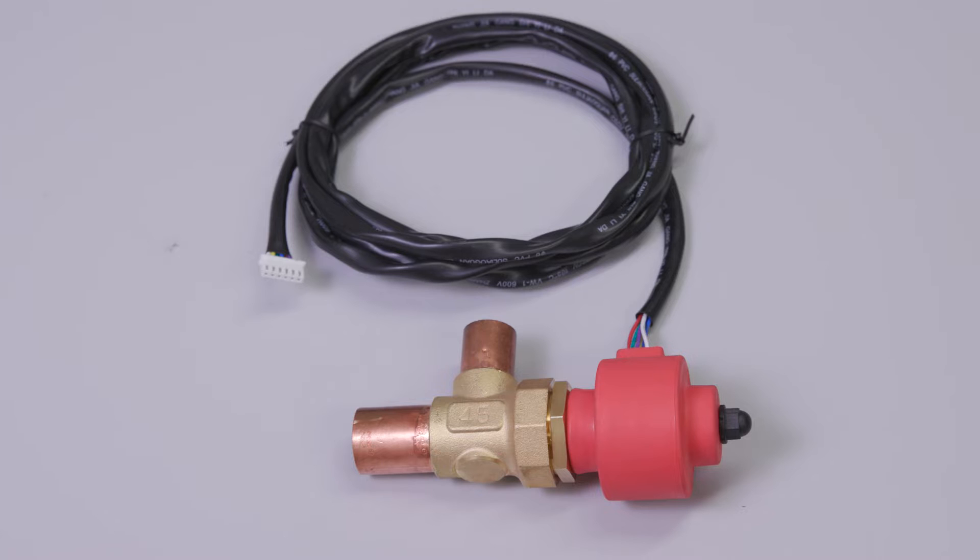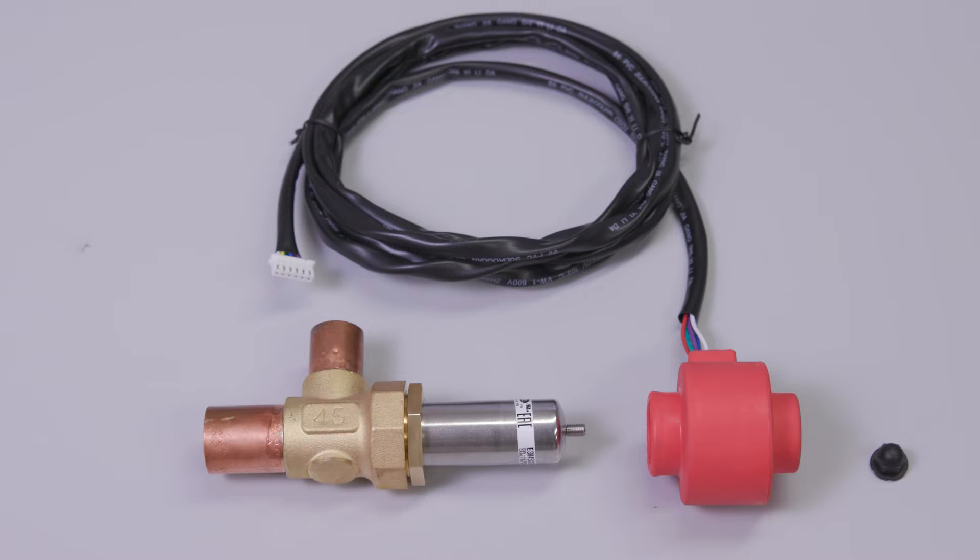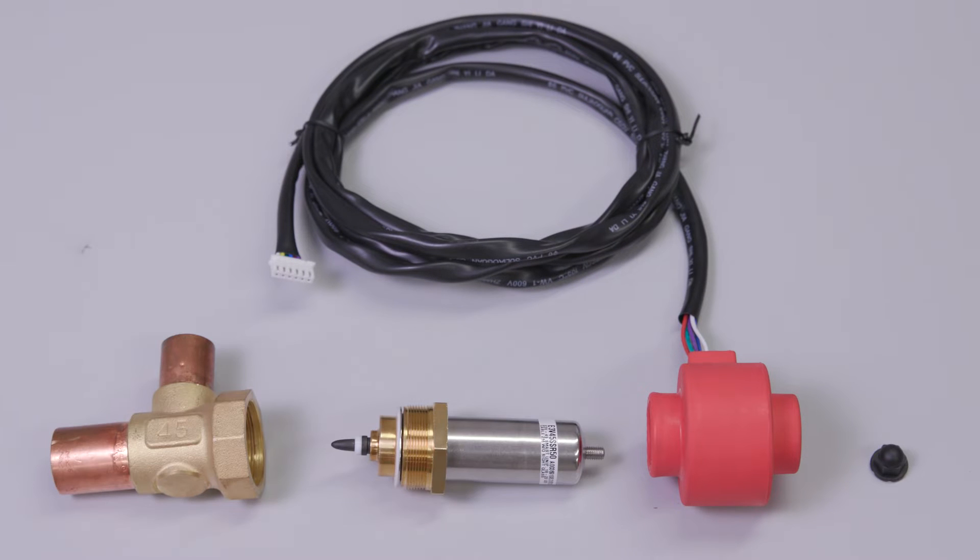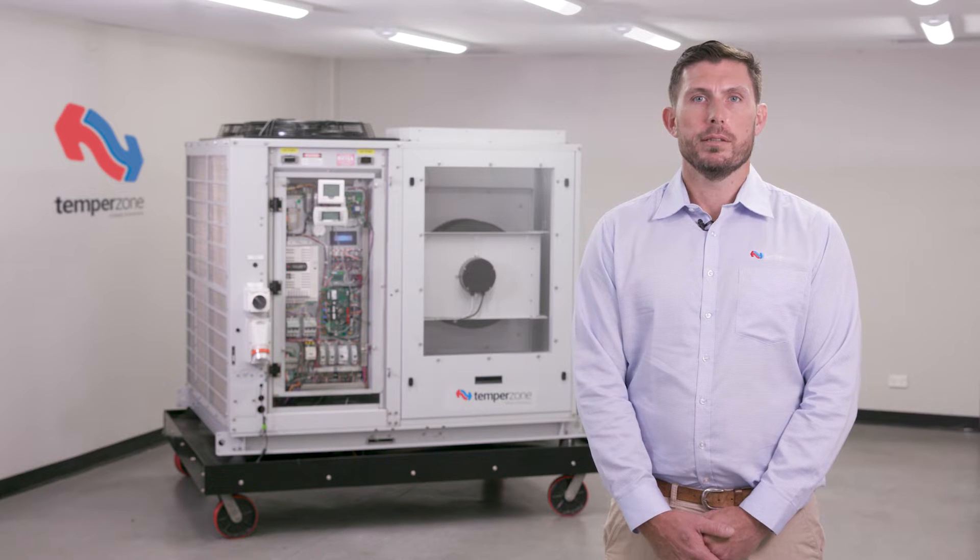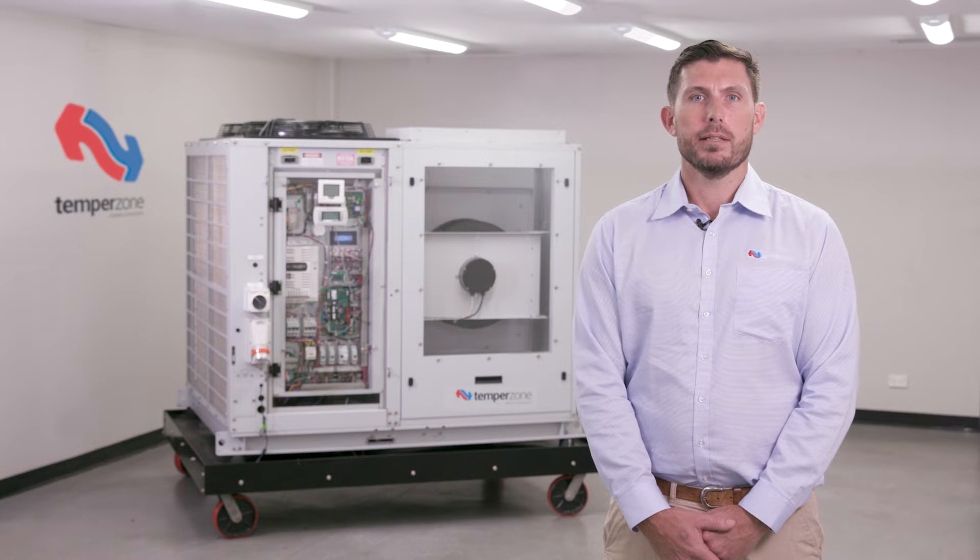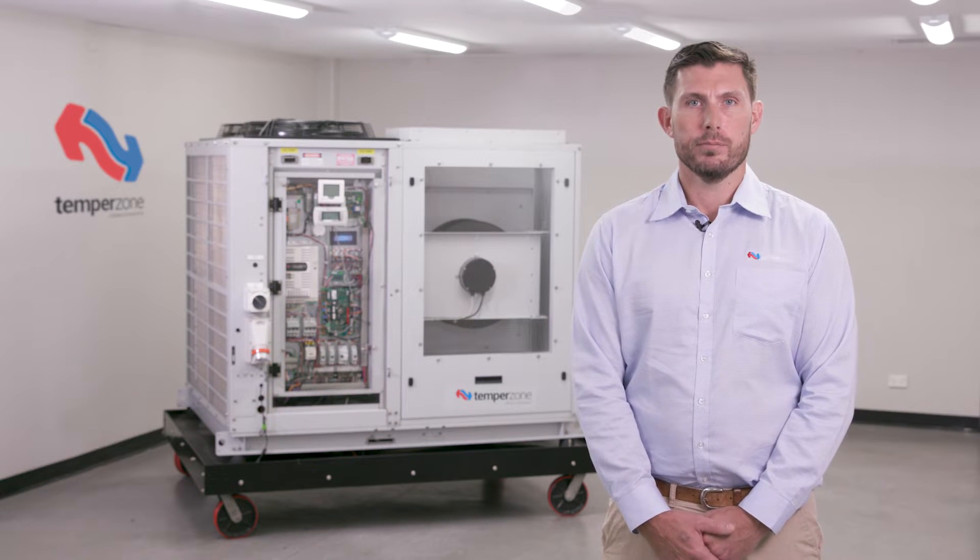Although an electronic expansion valve looks similar in appearance to a common solenoid valve, the method of operation is very different. Normal solenoid operation energizes a coil that electromagnetically opens and closes a plunger. Operation can either be 100% open or 0% open.